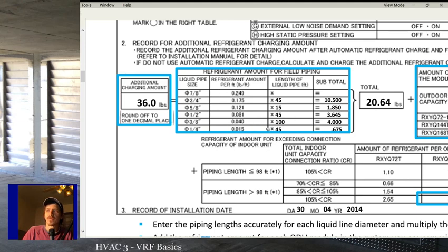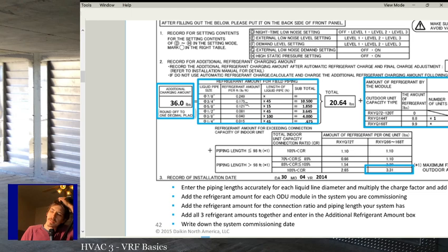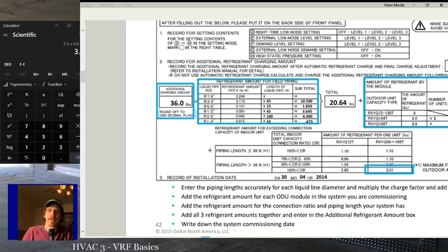0.015 pounds per foot 1/4, 0.04 pounds per foot 3/8, 0.08 pounds per foot 1/2 inch, 0.121 pounds per foot 5/8, 0.175 pounds per foot 3/4, 0.249 pounds per foot on 7/8. And that's probably close for just about every other system you work on, because no matter what system you're working on, besides what they added in for, which is usually 15 or 20 feet of line set from the factory, you need to add charge because of the line set, right? So you add that charge because of the line set.